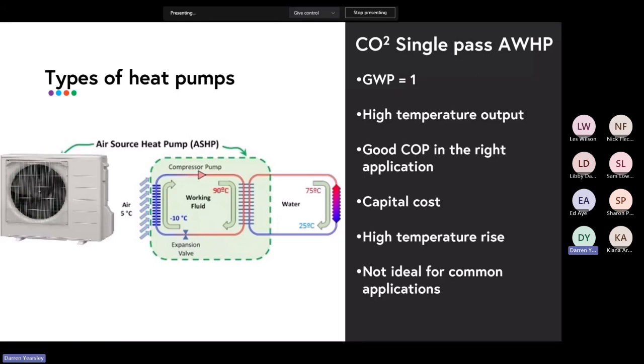And so now when you have a look at the duty cycle, you'll still have a significant amount of energy which you're putting into the system during recovery. So you'll serve your hot water for the building. Then over the next 2 to 3 hours, you'll be recovering those storages and you need to get them back up to 65 degrees to sterilize them. During that time, as the delta T across the appliance gets compressed, then the efficiency of a CO2 appliance goes down significantly. So because you no longer have an unlimited supply of 20-degree water available to be putting through your heat pump, now you're operating on your storage temperature, and your storage temperature obviously goes up as you get closer to the 65-degree target in your cylinders.